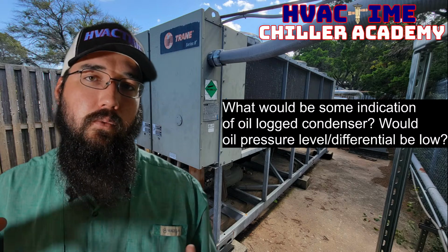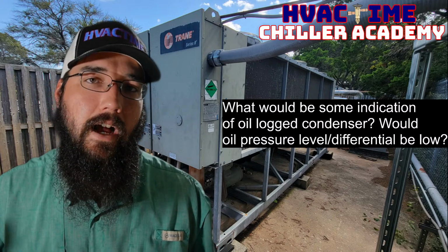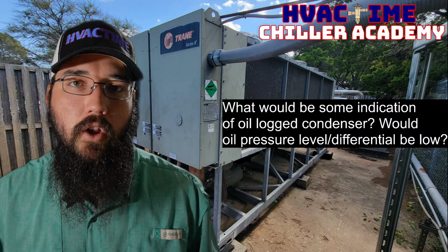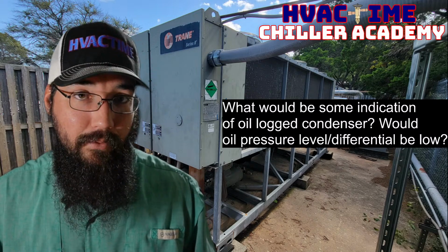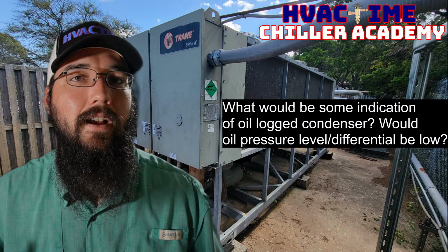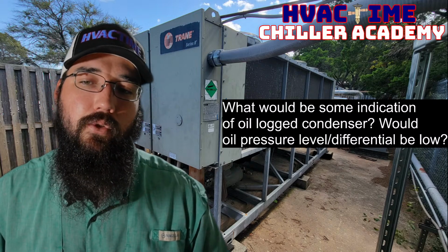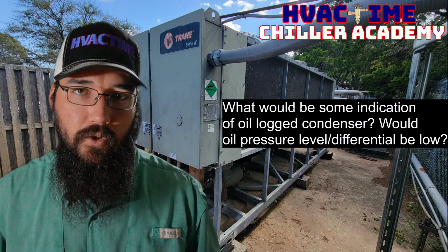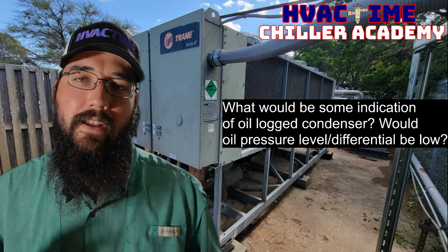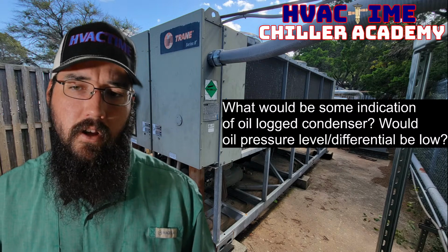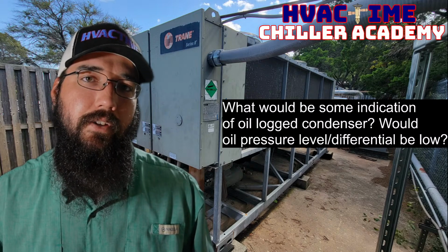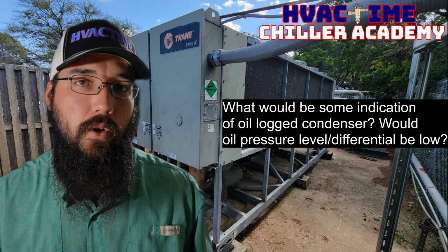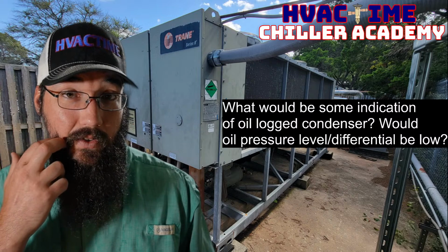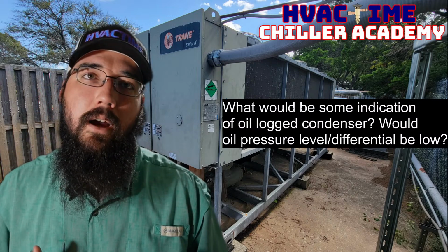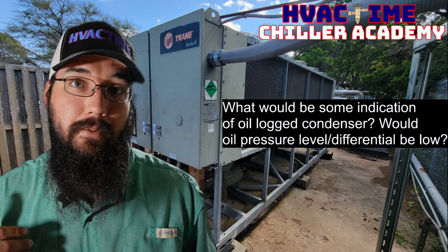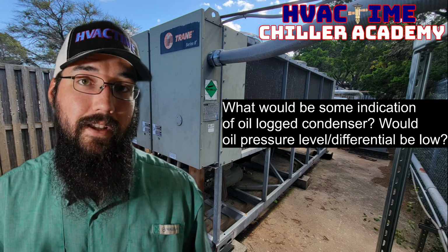And you'll also, in the nature of being a high approach value, have lower saturations on the evaporator specifically, right? So this is all collecting there. Now, how that relates to the condenser. There are circumstances where I've had condensers begin to struggle with oil logging. Usually I've found that it's when there's a high oil charge, there's just too much oil in the system, or we're not maintaining a high enough head pressure to maintain velocity through the condenser side of it.